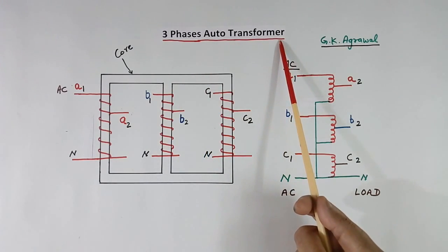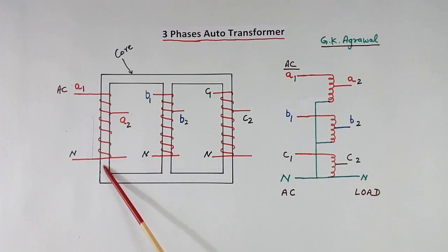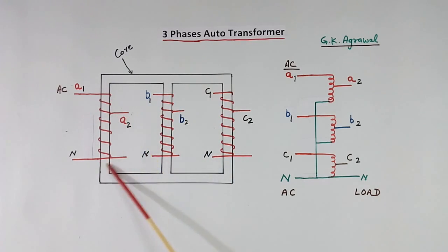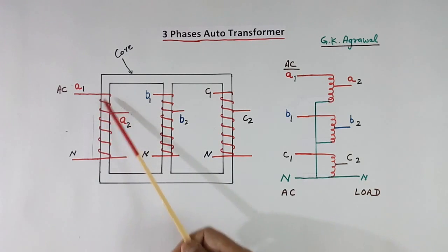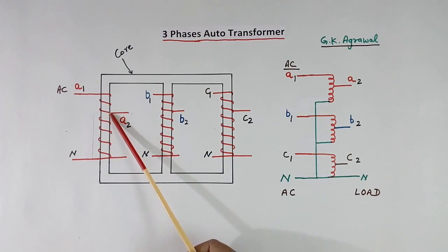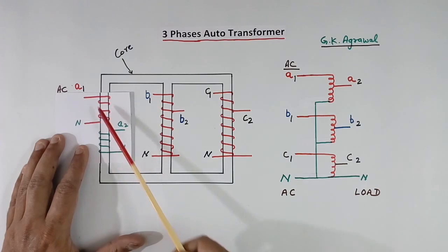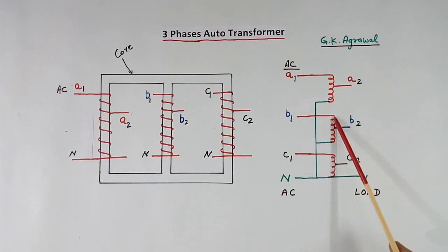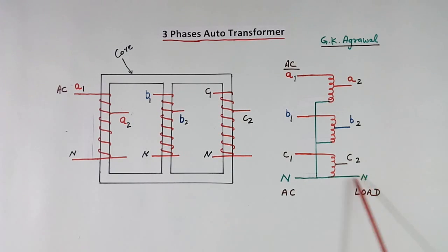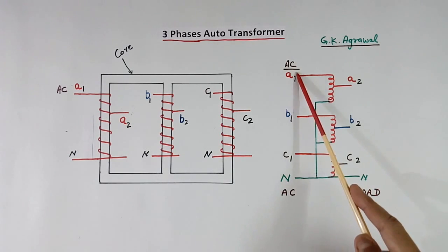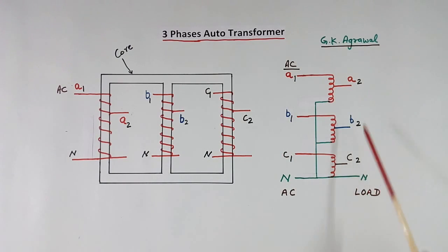This is a 3-phase auto transformer. This is the core and it has 3 windings — one for phase A, one for phase B, one for phase C. Each winding has only 1 coil, not 2. From that winding, AC input will be connected and at the tapping, the output load will be connected. In a normal transformer there will be 2 windings, primary and secondary, but here only one. One terminal of each winding is connected together and connected to neutral — this is a star connection. AC input is given here and load is connected here at A2, B2, and C2 in star mode.